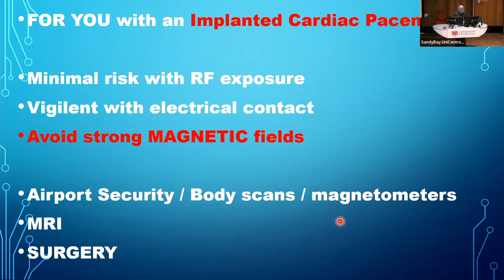Of course, if you put the magnet on, the machine goes into its fixed rate, and it exposes you as a patient to the R-on-T phenomenon, which we were trying to avoid by putting demand pacing in the first place. But it's only ever done when you're under highly monitored conditions, so it's quite safe, and it's done routinely. But there are large magnetic fields in other places like MRI scanners and airport body scanners and magnetometers and things. So you do have to be very careful that you don't get any fixed magnetic fields near your pacemaker.